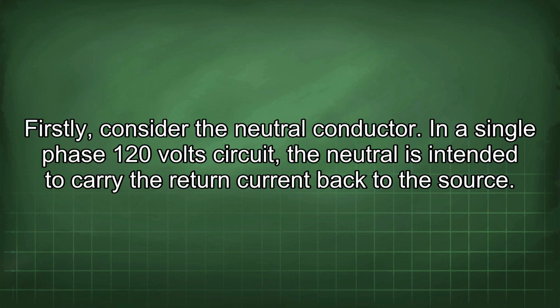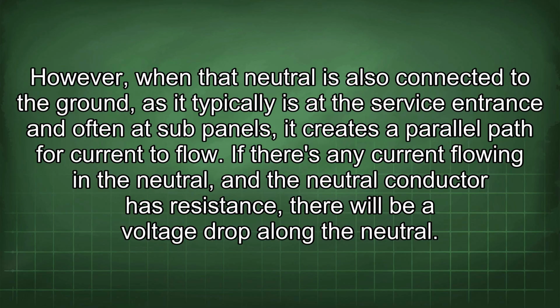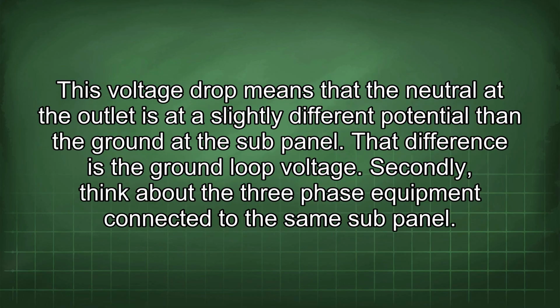In a single-phase 120-volt circuit, the neutral is intended to carry the return current back to the source. However, when that neutral is also connected to the ground, as it typically is at the service entrance and often at sub-panels, it creates a parallel path for current to flow. If there is any current flowing in the neutral, and the neutral conductor has resistance, there will be a voltage drop along the neutral. This voltage drop means that the neutral at the outlet is at a slightly different potential than the ground at the sub-panel. That difference is the ground loop voltage.